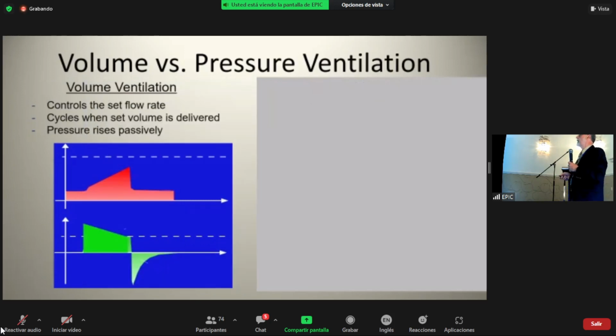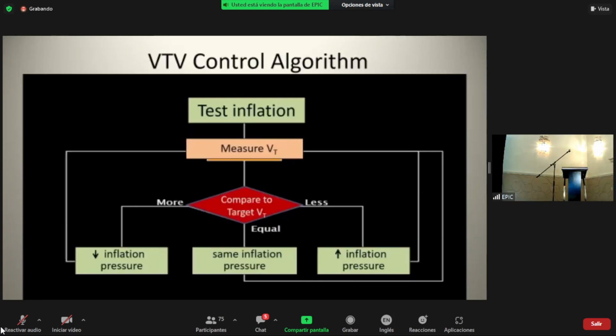With volume controlled ventilation, there is a fixed volume that the ventilator will deliver. It does so by generating a constant or slightly decelerating flow, and that flow continues until the volume is delivered, and then the ventilator cycles off and pressure rises passively and reaches peak just before exhalation. It's a derived variable. There is no direct control over that. And so the lungs fill fully only at the very end of the cycle. And so it's a different flow pattern. And so this is how pretty much all of the volume targeted modes work now.